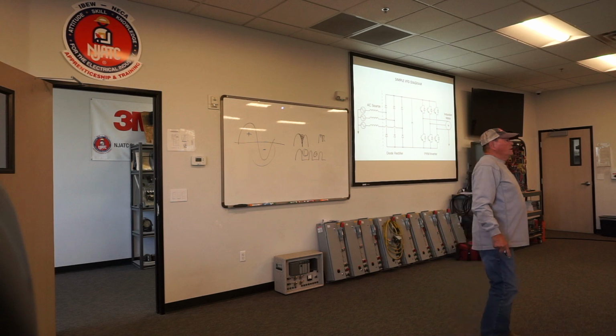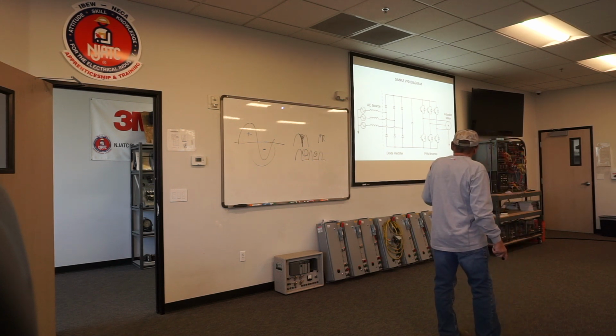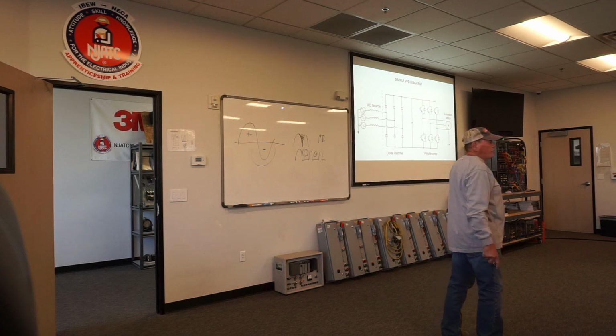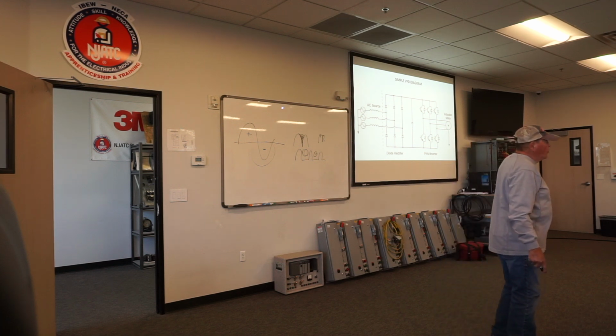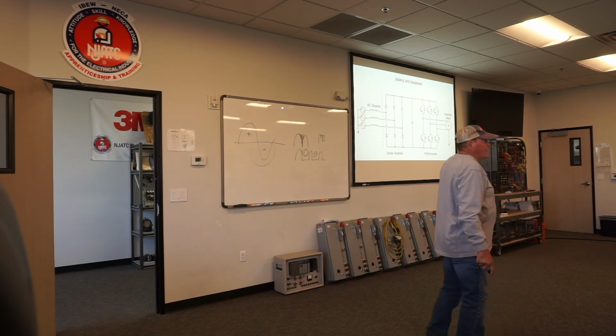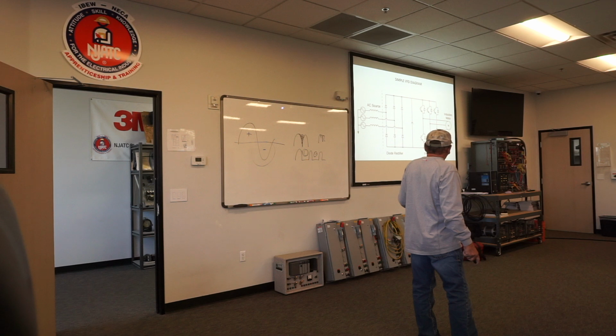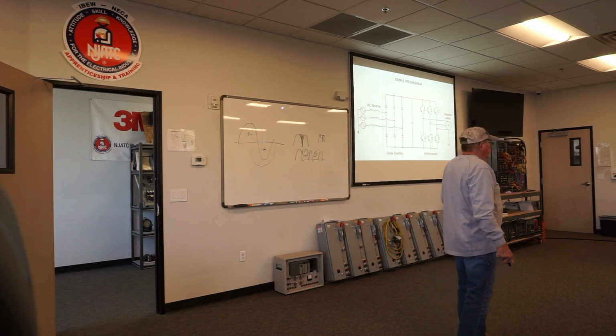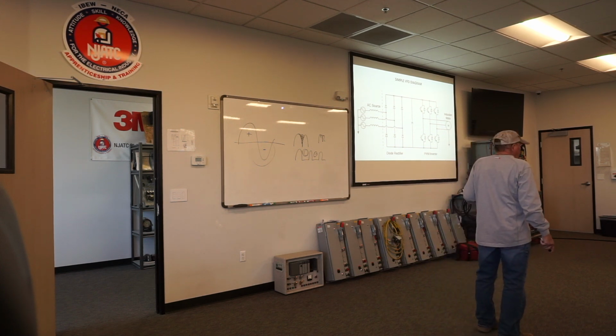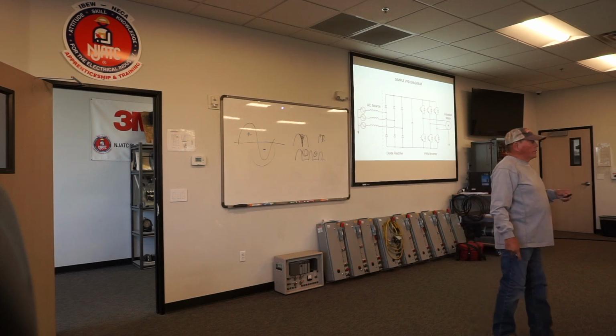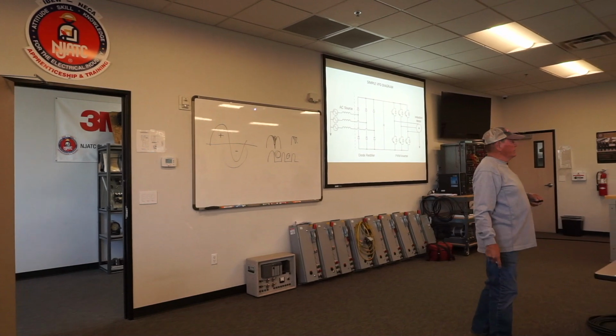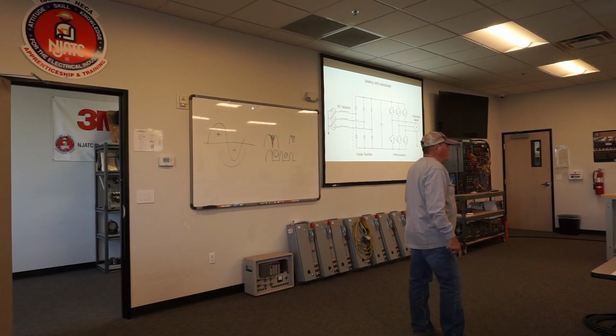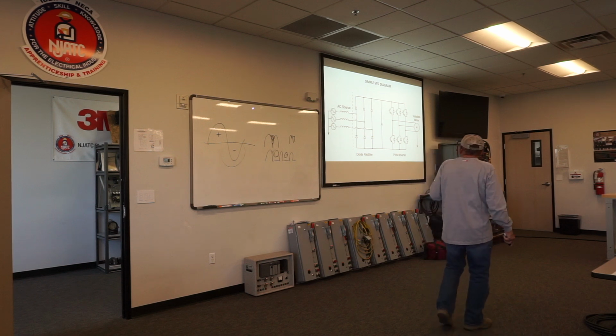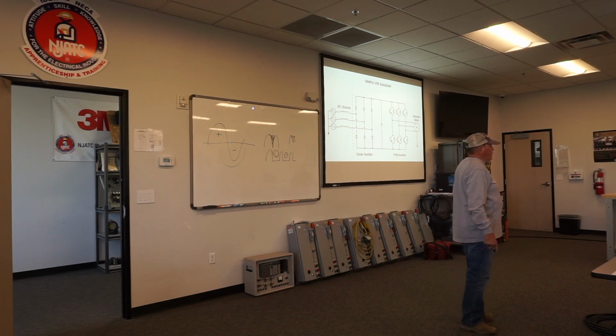Make sense? And that's why the weakest link in a VFD is the capacitor, because it's doing all the work. So when drives fail, quite likely it's going to start the failure here, because the more work this capacitor does, the hotter it gets. And as that heat generates, you're either going to get a warning on the drive saying high temperature or voltage failure. You'll get some kind of a fault because the drive's got to protect itself.